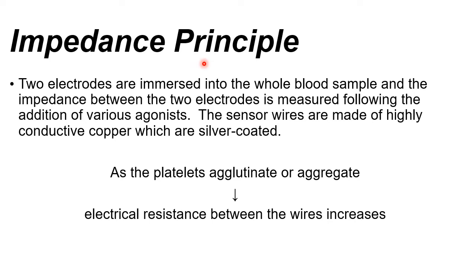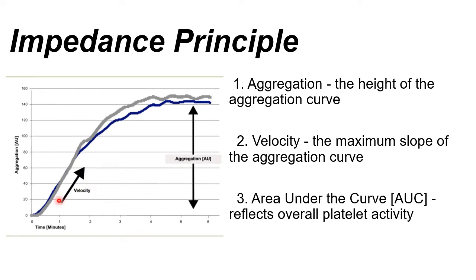For the impedance principle, it can sense platelet activity. More activity produces a larger electrical resistance. When the agonist is added, differences in electrical resistance begin — more agglutination produces more resistance. On the impedance graph, the x-axis is time and the y-axis is the amount of platelet aggregation activity. Note that for light absorbance the curve goes downward, while for impedance the curve goes upward.